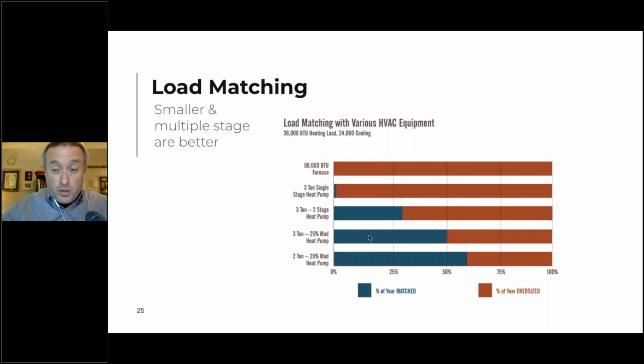And if we really want to do a good job, we actually undersize the HVAC. So we put a 2-ton in, and for heat load, when we can't make up for it, we use resistance backup. And that may sound utterly terrifying, and trust me, for the first couple that we did, it was, but it's not that bad once you get used to it, but you need to trust your load calculations.